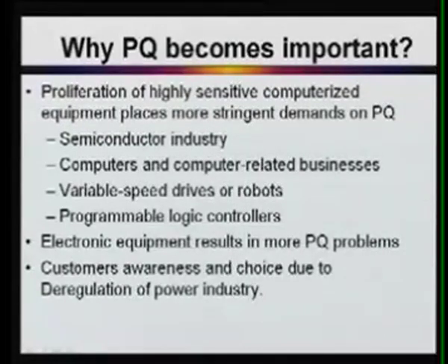So voltage dip is basically maloperation of sensing circuitry in computers and variable speed drives. For voltage swell, if voltage is more than the normal 1 per unit, as I said, if it is 1.1 per unit to 1.8 per unit for a duration of less than 1 minute, it may damage the insulation, because high voltage may cause damage to insulation, and therefore it is a permanent fault.